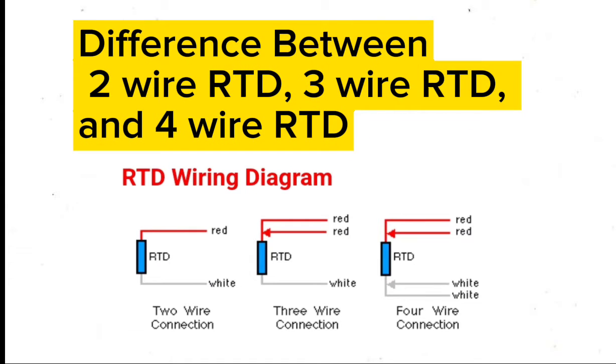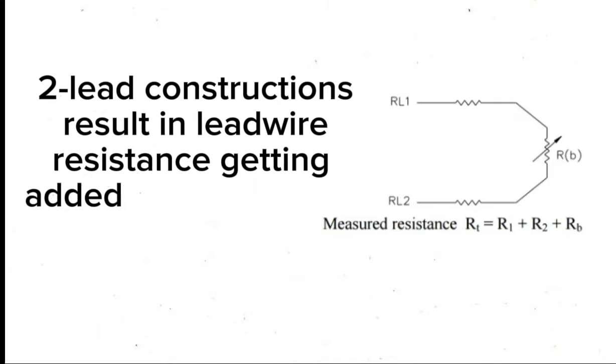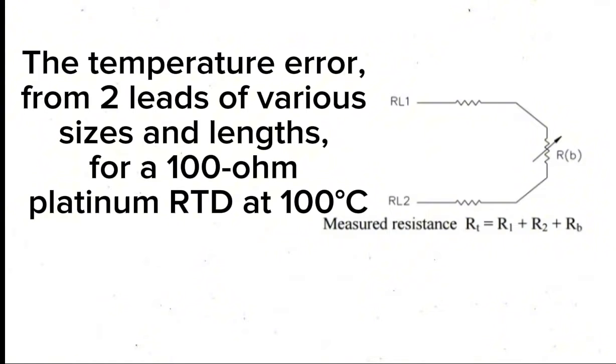The difference between two-wire, three-wire, and four-wire RTD: two-lead constructions result in lead wire resistance being added to the element resistance. The temperature error from two leads of various sizes and lengths for a 100-ohm platinum RTD at 100°C is significant.